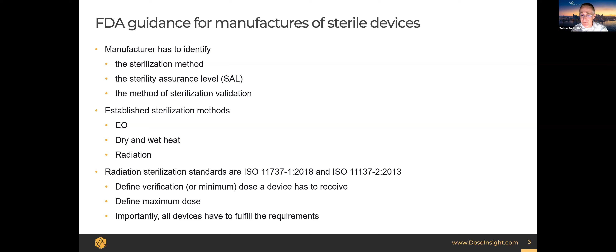And you also have to define a maximum dose. The reason for that is that the device or the materials can be damaged if you go over a certain dose threshold. The important thing to keep in mind is that it is not enough to just assure that one device can be sterilized. You have to ensure that the whole package of devices that you put in the beam is sterilized. So that is important to keep in mind.